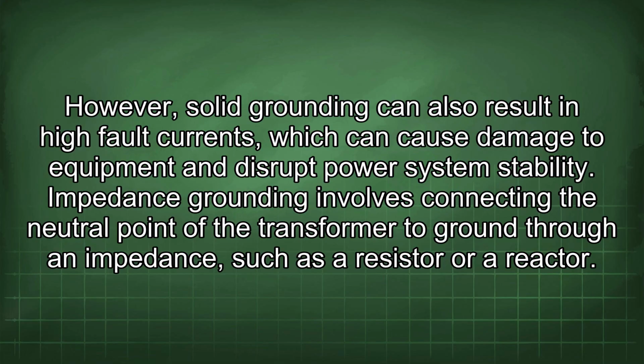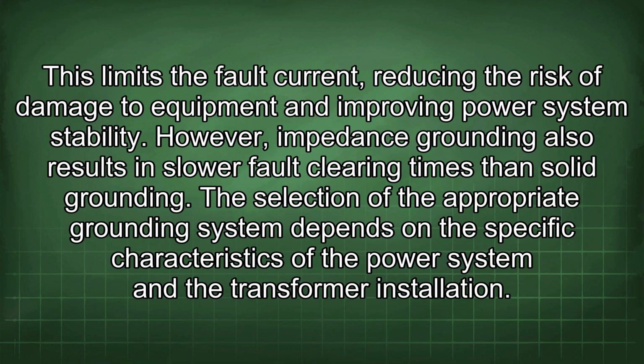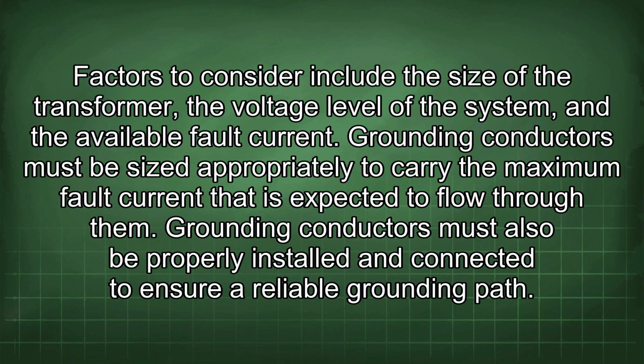Impedance grounding involves connecting the neutral point of the transformer to ground through an impedance, such as a resistor or a reactor. This limits the fault current, reducing the risk of damage to equipment and improving power system stability. However, impedance grounding also results in slower fault clearing times than solid grounding. The selection of the appropriate grounding system depends on the specific characteristics of the power system and the transformer installation. Factors to consider include the size of the transformer, the voltage level of the system, and the available fault current. Grounding conductors must be sized appropriately to carry the maximum fault current that is expected to flow through them. Grounding conductors must also be properly installed and connected to ensure a reliable grounding path.